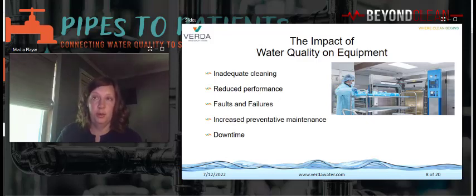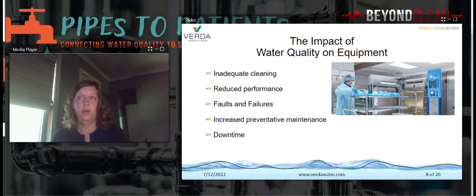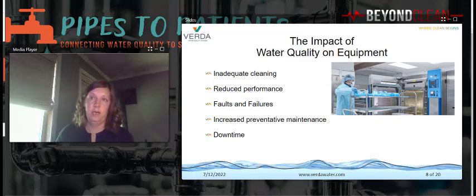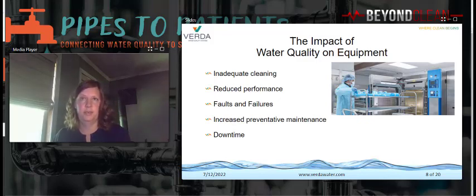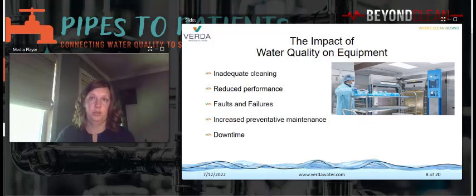Chlorinated feed water damages the RO membranes, and if the chlorine level or the chloride level is high enough, the RO membranes wouldn't remove enough to meet the purified water requirements for final rinsing. And while not a water chemistry parameter, feed water pressure to the RO also needs to be maintained within the OEM specified range, usually no less than 20 to 25 psi. For UV irradiation systems, they often have pH, water hardness, ionic contaminants, TSS, total suspended solids, and turbidity requirements to ensure that the UV transmission through the water is adequate to destroy and inactivate the microorganisms.